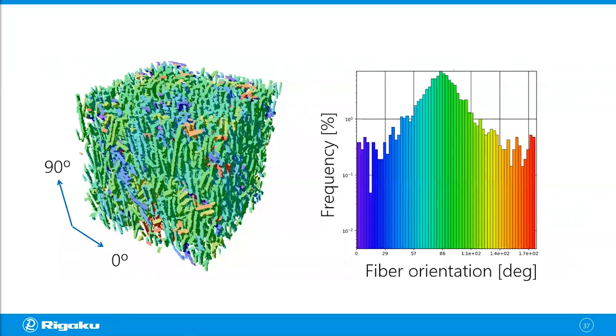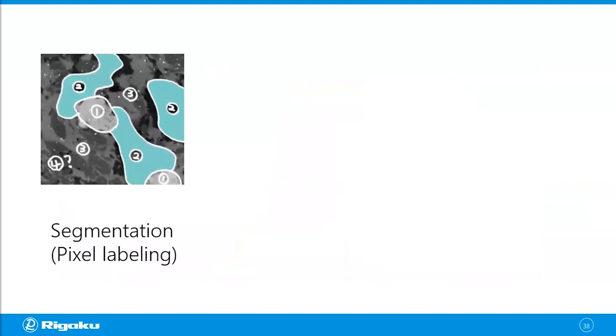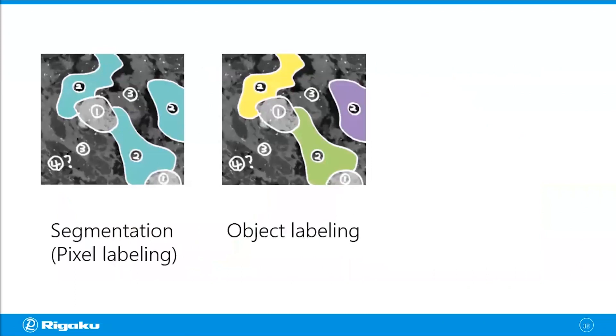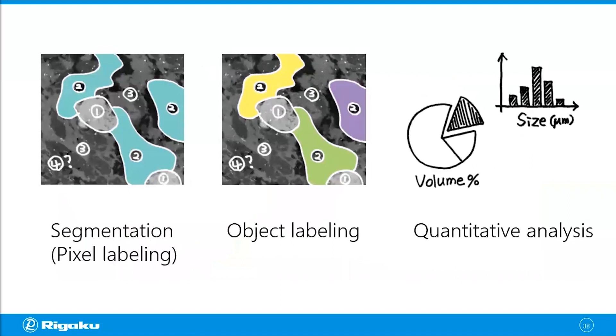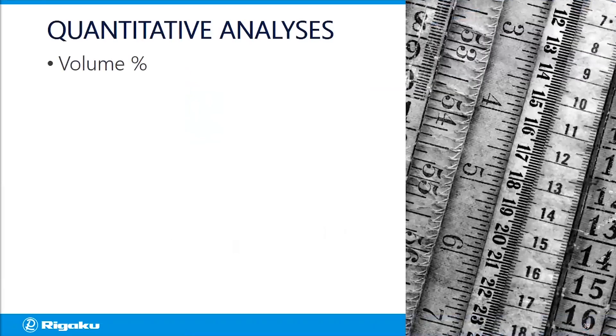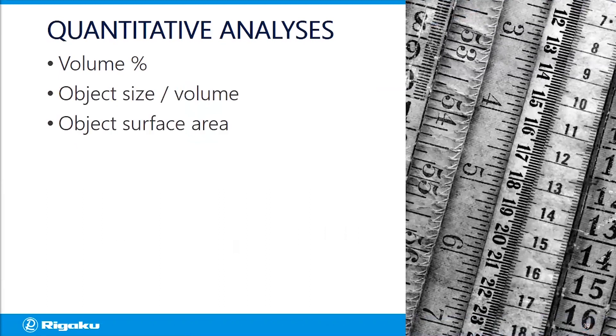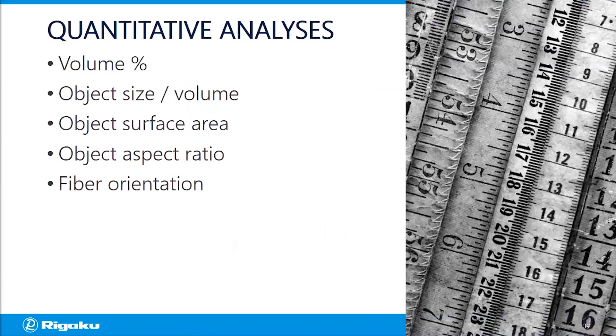For example, you can make a histogram of void volume distribution to see how large the voids are and how many you have. Similarly, you can look at the fibers and analyze fiber orientation distribution. This is the main flow of X-ray CT data analysis: start with the raw image, segment it into different phases, label individual objects within each phase, then move on to quantitative analysis. Typical analyses include volume percentage, object size, volume, surface area, aspect ratio, orientation distribution, and layer thickness distribution.